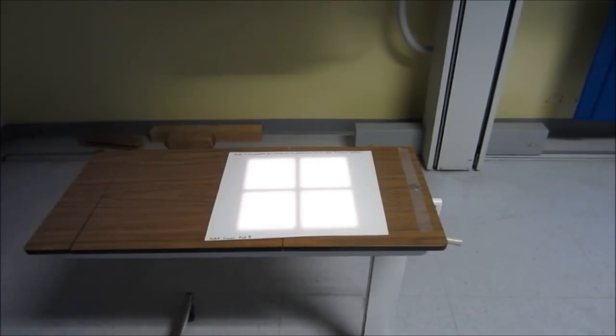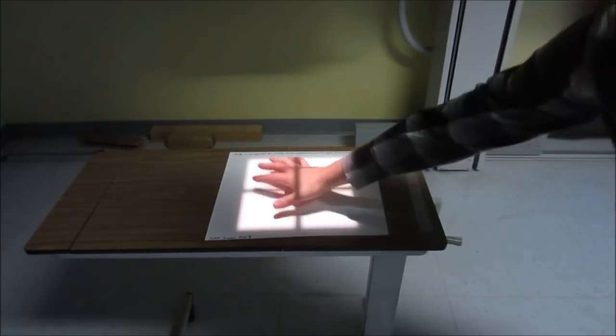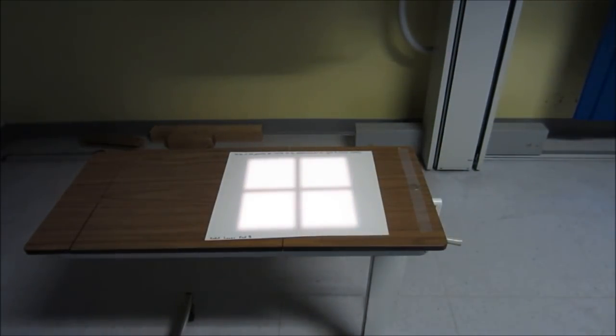You can see the light field on the intensifier screen. In practice, the technologists would use this light field to get an idea where the X-rays are going to strike the patient. For example, if we're doing a hand X-ray, make sure the hand's covered in the X-ray and collimate down to reduce scatter and things like that.